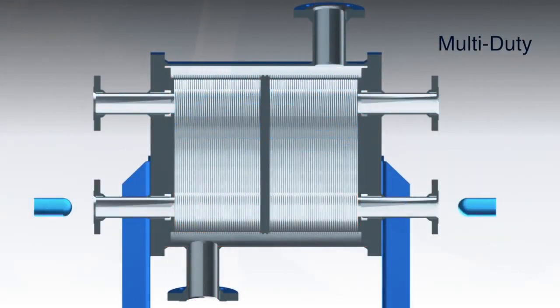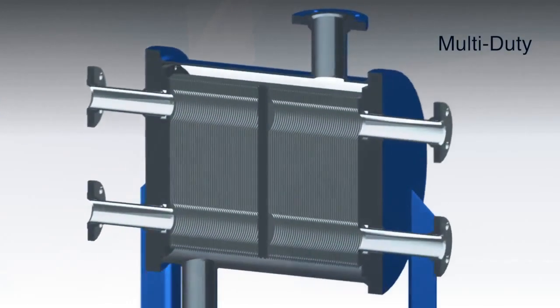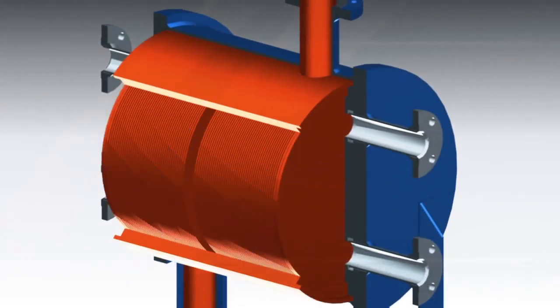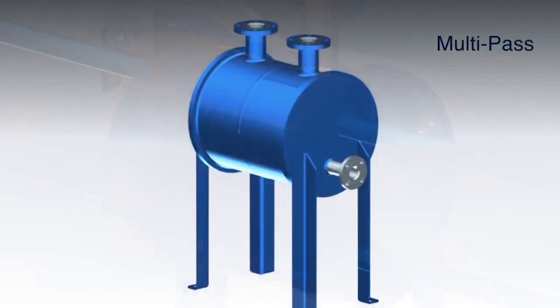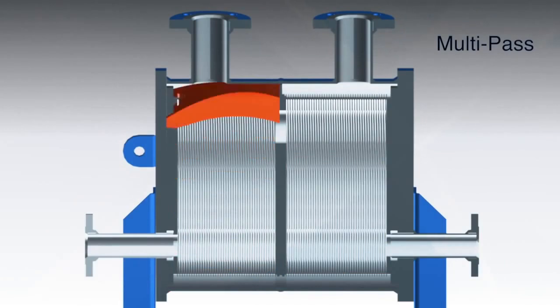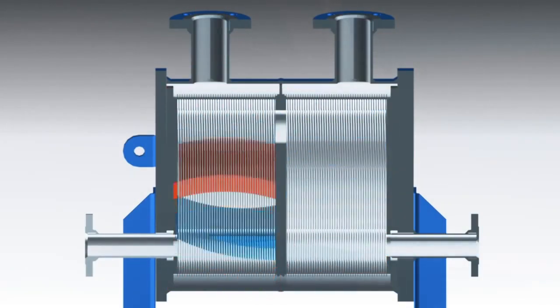In this instance, compact size and versatility combine to yield an efficient evaporator and receiver system containing an oblong thermal element. Here's more versatility, particularly for process skids: the multi-duty exchanger has two separate plate packs that share one shell. Multi-pass configurations accommodate particular heat transfer and pressure drop requirements by grouping plates in co-current or counter-current flow duties.